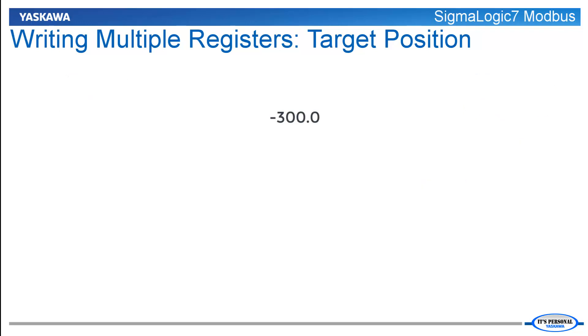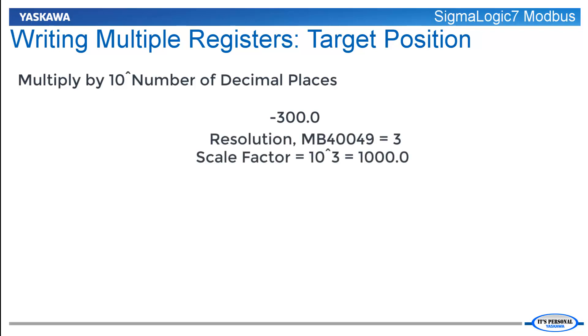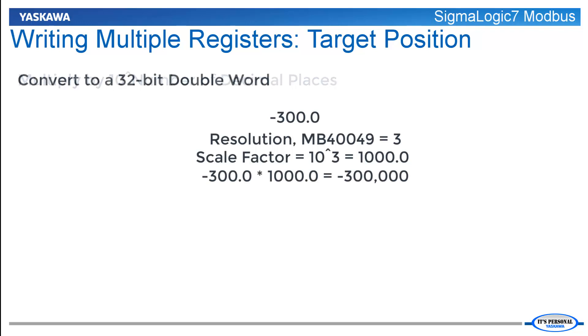Here is an example of writing negative 300 to the target position registers. The first step is to scale the value by 10 raised to the number of implied decimal places to create a 32-bit signed integer. In this example, the resolution register is set to 3, so the scale factor is 10 raised to the third power, which equals 1000. We multiply the target position by the scale factor to arrive at an integer value of negative 300,000.